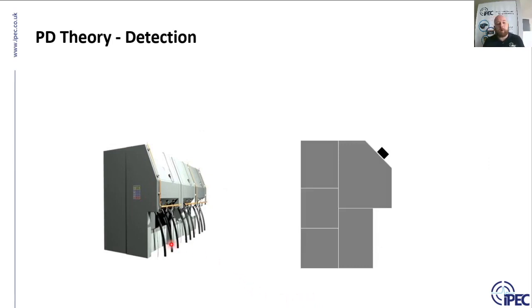So what happens is very similar to cable PD actually, just in a different enclosure, a different environment. When PD occurs in a high voltage component, the signal will dissipate from the source, and it will be induced on the inside of the panels within the switchgear, and then it'll travel away from the PD source. So again, just like cables, it's trapped inside, traveling along the surface, and it comes out through the gaps in the panels. Where two panels are attached together, it travels out through the gaps and along the outer surface of the equipment, and then it travels across the surface of the TEV sensor, be that built into an instrument or physically attached. And then that signal is induced on the sensor.